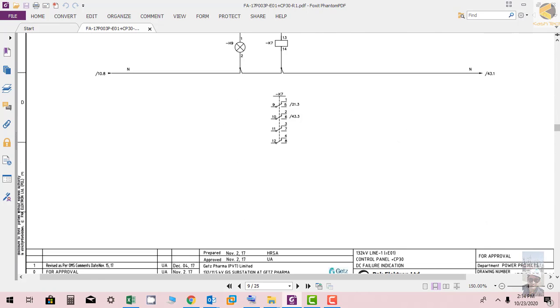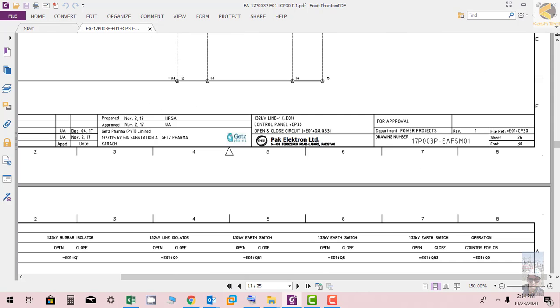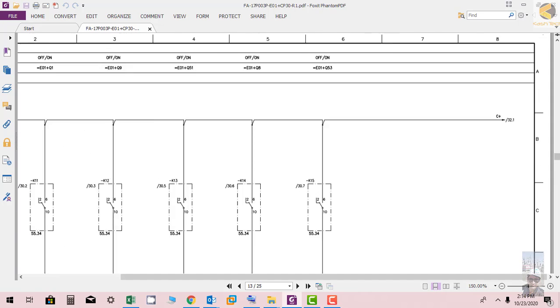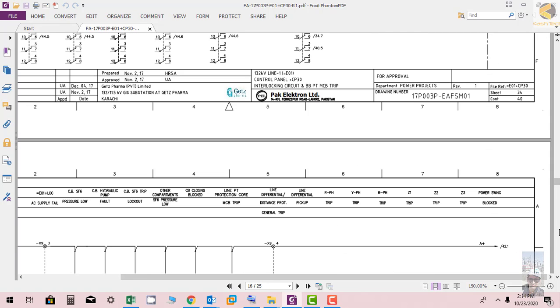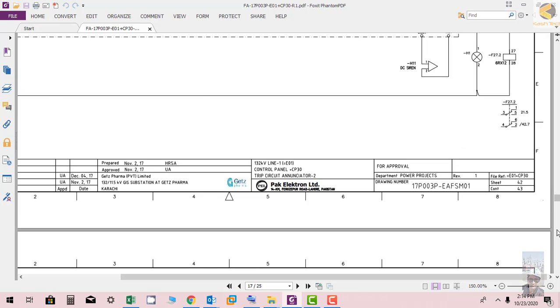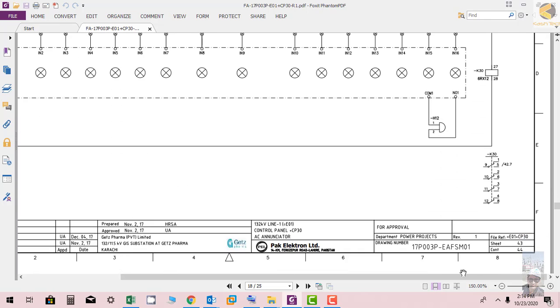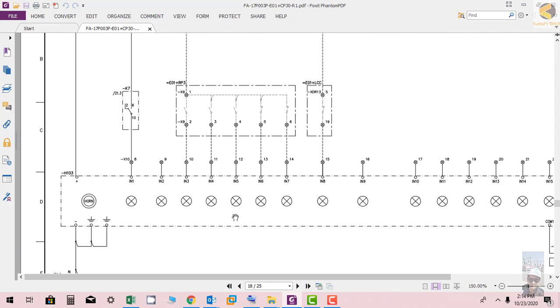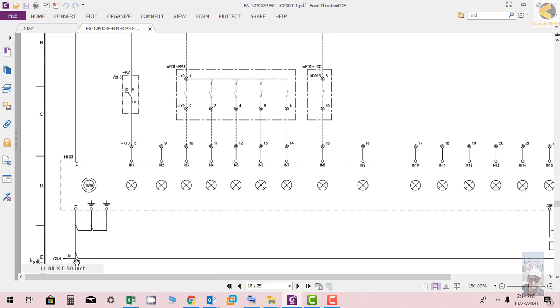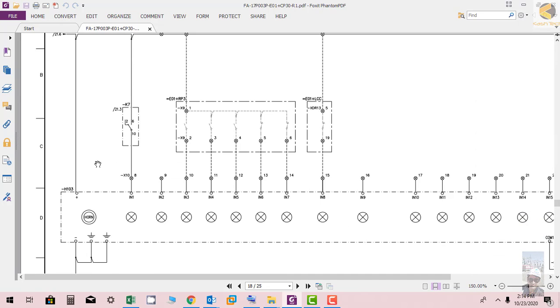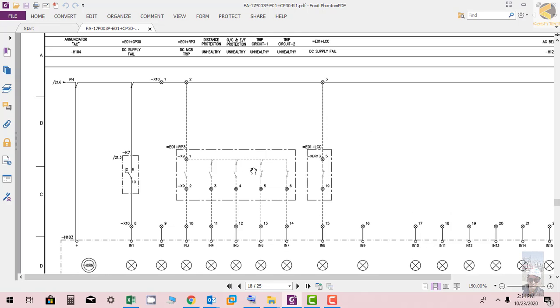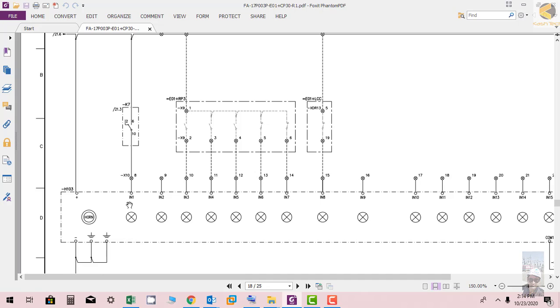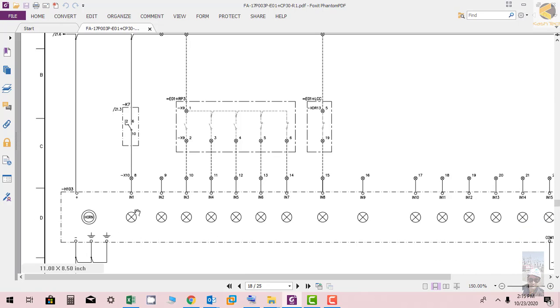Further it's going to sheet number 43.1, so let's go to sheet number 43.1. This is sheet number 43. AC supply is coming here, so this is the phase and basically the supply is connected to AC annunciator power supply module. Then further you can see the AC supply is distributed to give connections to input of AC annunciator. For example, if the supply is fail, K7 that I have shown you picked up and the light ion one will be on.